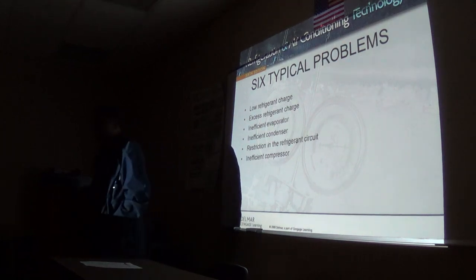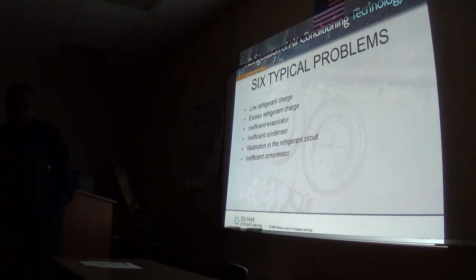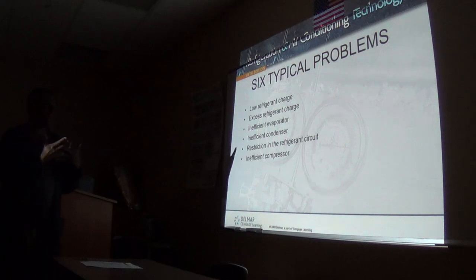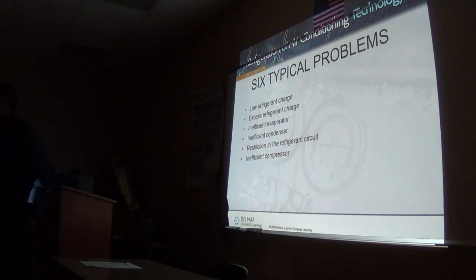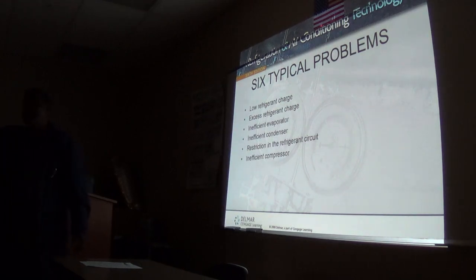An inefficient compressor, though, does it just become worn over time? It's going to be sized for the system, right? So it just becomes worn because of other things going wrong in the system? Really, an inefficient compressor means that the compressor has worn out to such a point where it's not pumping the amount of refrigerant I need. So it's not keeping up the, what we call, the mass flow rate. Just wear and tear.